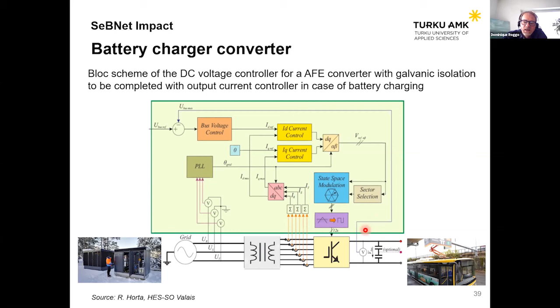I have listed them here. The most important factors are how far the bus charging installation is from the bus, or actually from the transformer station, how many converters are connected in parallel, and whether harmonics are already present on the grid so that the controller would react.